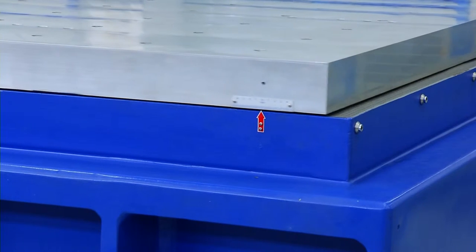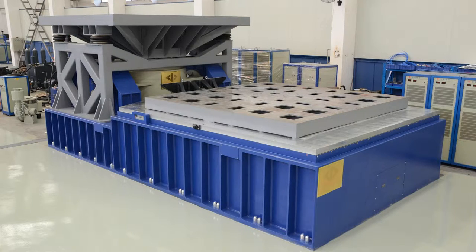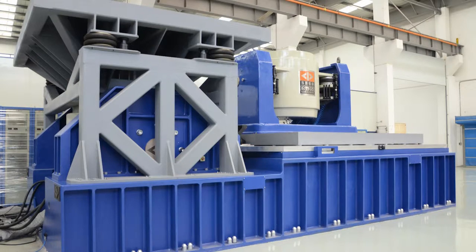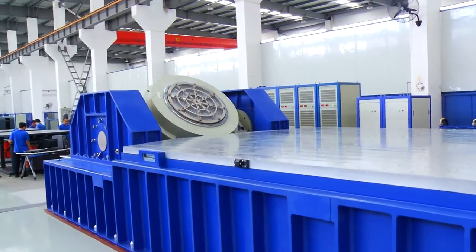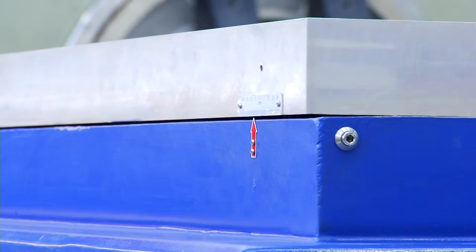Meanwhile, the system is configured with 3.2 meter by 3.8 meter vertical head expander, which increases the load ability and eccentric moment. It provides a reliable carrier for large specimens, especially for overall tests in aerospace.